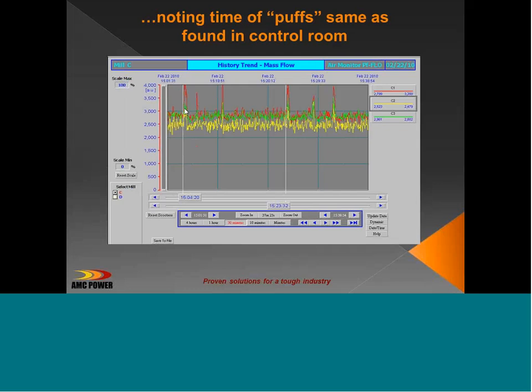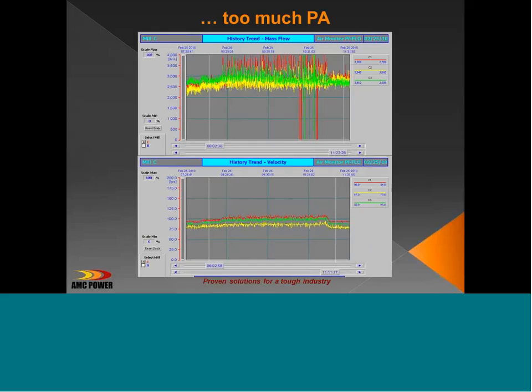What we then did for them is to follow what an operator normally does when they have these puffs. We can see that whatever the operator was doing when these puffs started to happen, they became very frequent, and on the bottom screen the coal velocities were increasing all this time. So the operator, when they started to have puffs, felt that adding more primary air would help solve the problem. The reality was it was making it worse. So we asked the operator, whatever you're doing, do the opposite. They decreased the primary air, which we can see in the bottom right. The velocity in the coal pipes decreases, and the surging or puffing abated. We still don't know exactly what caused the problem, but we knew what was certainly making it worse and how to prevent it.